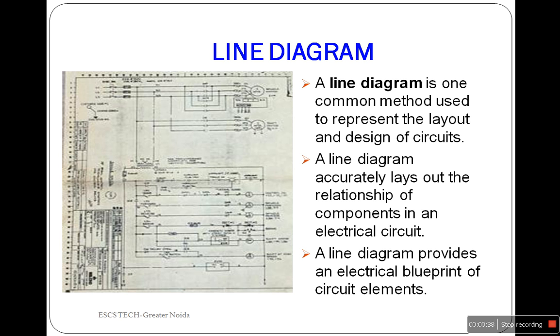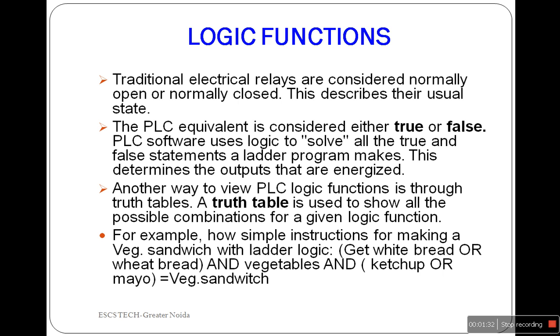Ladder logic is a PLC programming language that simulates the functionality of relay circuits. Ladder logic is based on line diagrams. A line diagram is an electrical blueprint that accurately lays out the relationship of components in a circuit. You can think of a line diagram the same way you would a blueprint in construction — both are key documents that explain the fundamental structure of a layout. A line diagram tells you what materials are involved and how the various devices and loads are connected to each other, making them very useful when designing control circuits and also a helpful reference when troubleshooting a malfunctioning circuit.